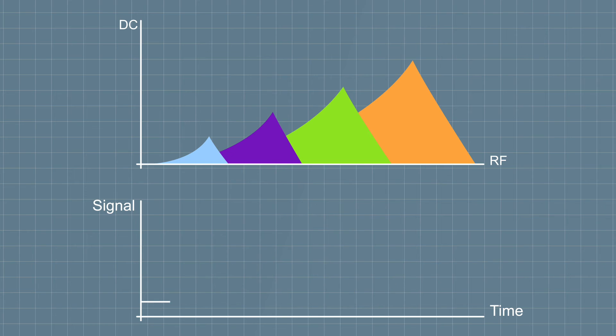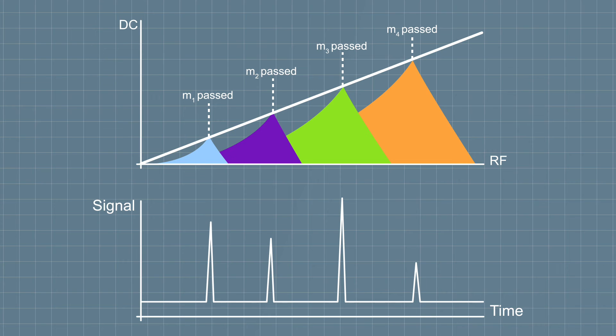We can also increase the DC to RF ratio to the point where the scan line crosses the very tips of the stability regions. As you can see, as we do that, the peak widths are reduced, therefore the resolution is increased. As we attempt to operate a quadrupole at higher and higher resolution, the transmission reduces because the entry conditions become more and more stringent. In other words, the ions must enter closer and closer to the central axis to make it through.